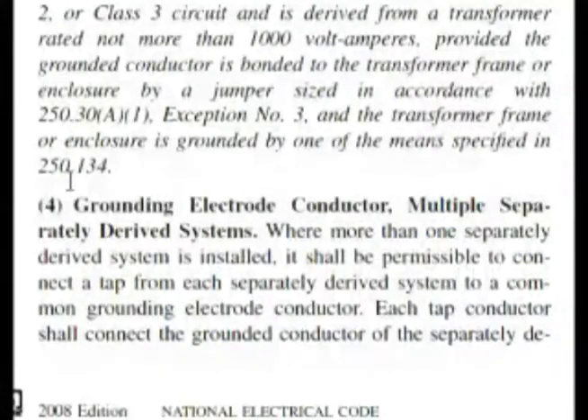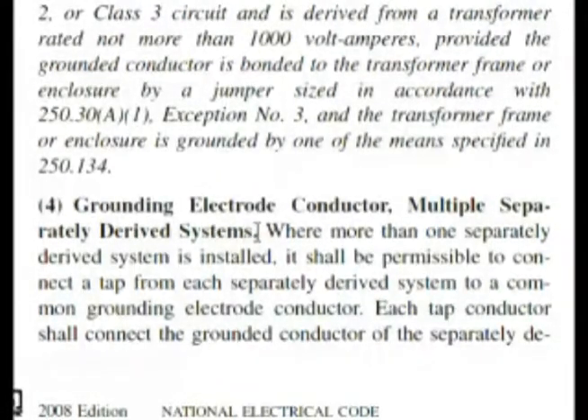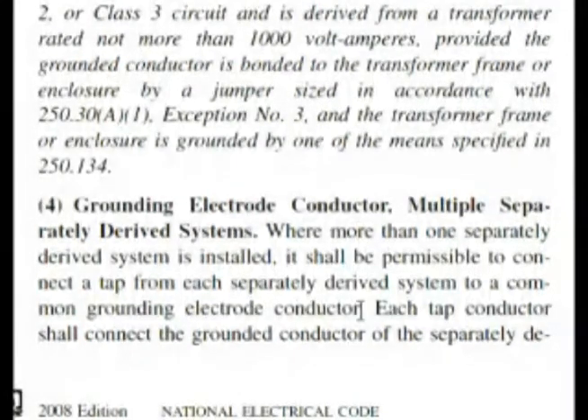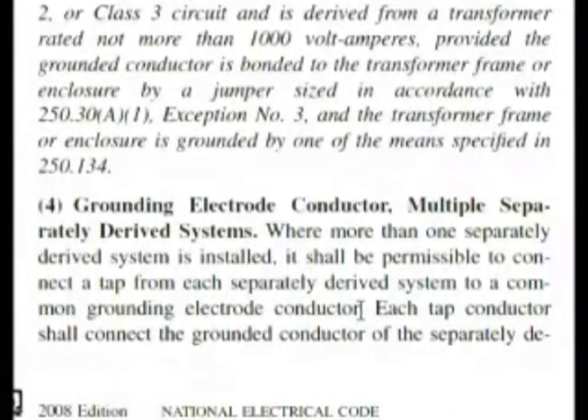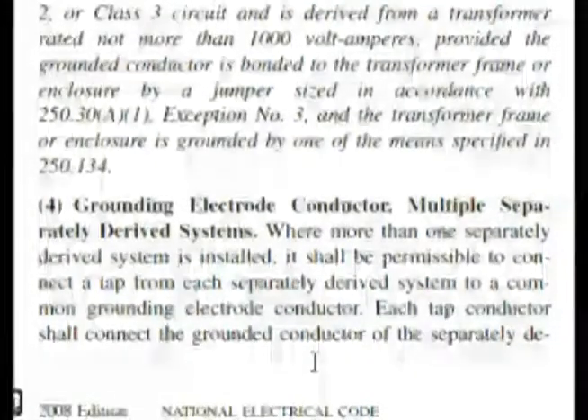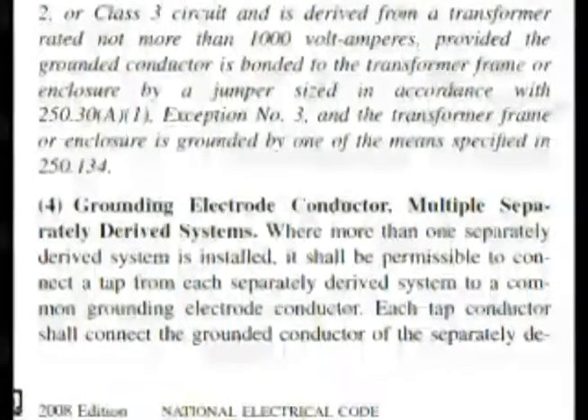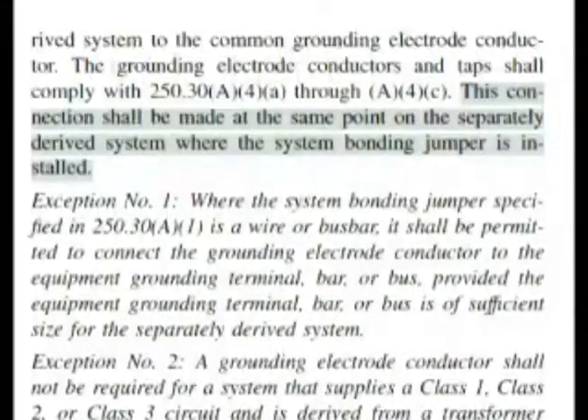Let's look at separately derived systems — it's 250.30(A)(4). Here we are in the code at 250.30(A)(4): Grounding electrode conductor, multiple separately derived systems. It says where more than one separately derived system is installed, it is permissible to connect the tap from each separately derived system to a common grounding electrode conductor. This is basically telling us it's permissible to do it, but our question is asking us what or how we should do it. We have to go to the top of the column on the same page and follow along in your book.